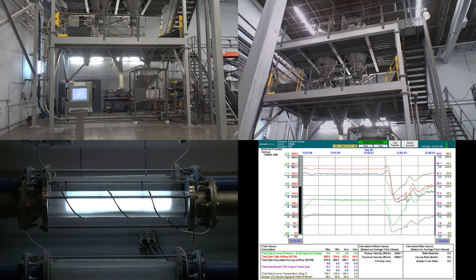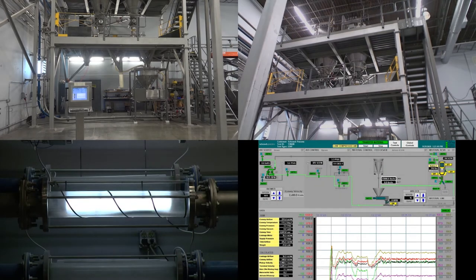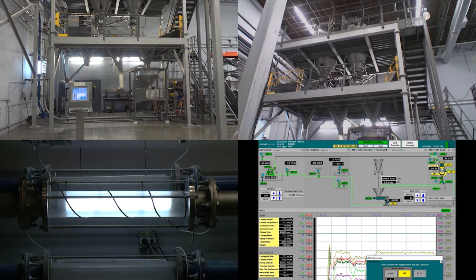Other influences like degradation and abrasion generally go down by the square of the velocity, so they would be reduced by at least half. In this next example, we are conveying at the same rate, but at a shorter distance. In a standard dilute phase system, this would cause the velocities to increase. With EDIP, we see a blower slow down to 32 hertz and maintain the same air velocity and yield the same conveying results.